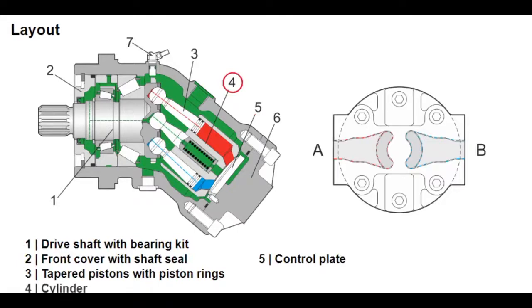Due to the bent axis design, torque is produced directly on the driveshaft. The pistons exert minimal lateral force on the cylinder, which reduces wear, increases efficiency, and improves starting torque. The port plate holds the rotary group in the housing and passes hydraulic fluid through two channels.